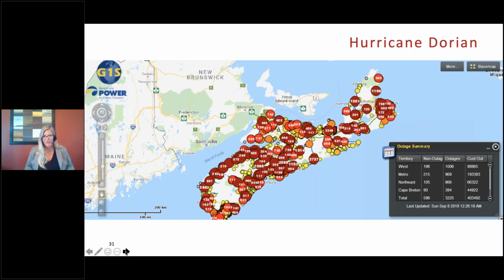Because of the nature of the protection and control design of the microgrid, it's designed to operate in the event of a loss of transmission or a loss of substation power. It's not designed to work if there's a fault potentially within the extent of the microgrid. Because Dorian was such a tree-related event and the line sensors weren't able to firmly locate the outages, and there were multiple outages, we decided it was safer not to action the microgrid during Dorian.